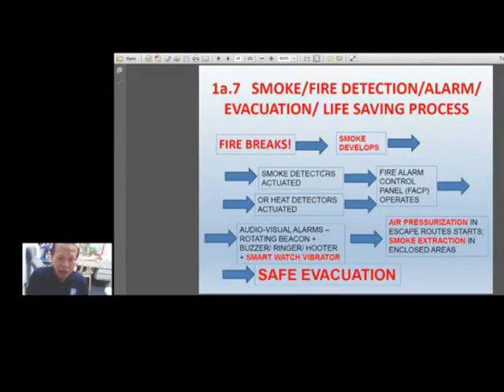So now let's analyze two slides which would explain the sequence of operation of a fire. I mentioned the first slide as the life-saving process: smoke, fire detection, alarm, evacuation. So when a fire breaks out, smoke develops, and smoke will be received by smoke detectors, and the detectors will actuate the fire alarm control panels.